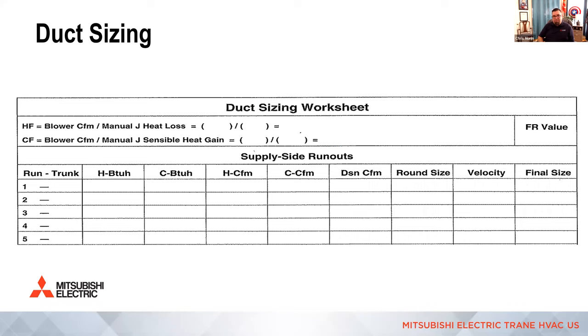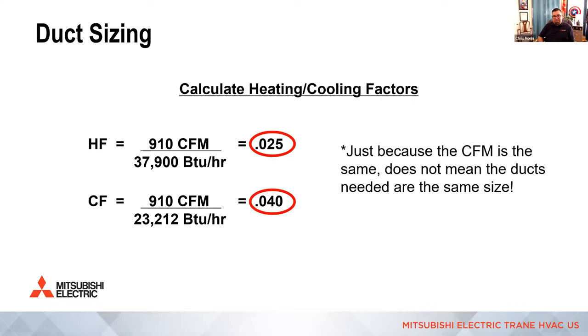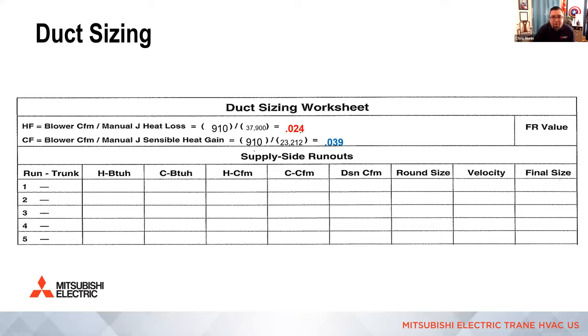Is that right? Oh my gosh. Sorry about that, guys. I'm off by 1/1000th on my worksheet. I don't think it's going to change the size of the runs, but I need to fix that for my max presentation. All right. And then, of course, we're going to transfer over that 0.09 friction loss with the bullhead tee that we added, right? That's our design friction loss. And then we're going to list each room that this is servicing. So this must be a ranch in this example, not a colonial like I was talking about before. But you can see a kitchen, a living room, and 3 bedrooms that we're servicing.